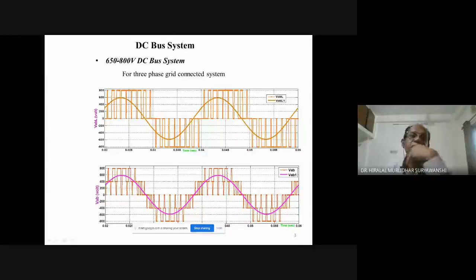Why is it 650 to 800? 800 is very ideal, so generally people use 800 volt. Sometimes 750, sometimes 800, but 800 is very good. Why is 800 required? The reason is, you can see here the inverter output voltage, that is 800 volt, right? Now what is the line to line voltage of the supply system? The line to line voltage of the supply system is √2 into 415. Now you multiply the 415 line to line voltage by √2. It comes to around 600 volt.